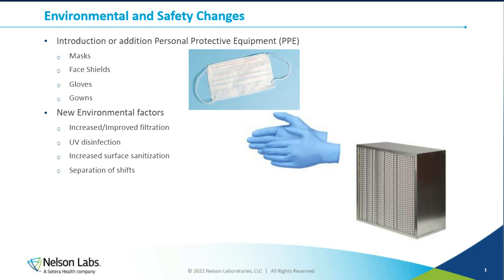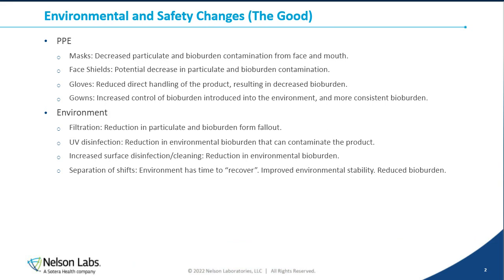My focus in particular is radiation sterilization, which is a bioburden-based sterilization method. Anytime we have a change in bioburden, since it is a bioburden-based sterilization, that can mean a fairly large effect. But it's also going to cascade to other sterilization modalities as well, and other aspects of product safety, such as endotoxins or particulates, as an example. So I like to break it down as the good, the bad, and the ugly. The good is when we implement PPE changes, when a lot of people added in items in order to protect their personnel from COVID, in a lot of cases, that also made some positive changes for the product.